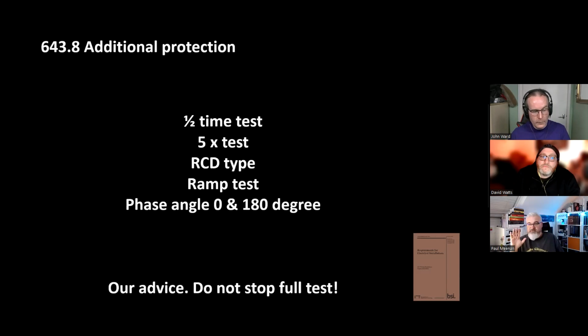The other thing I would really like to get on my soapbox about is, if we start cutting testing down to a minimum and we test at the terminals, then there is no point to it. I was taught that when I go out, I interrogate connection of the protective conductor at each point. Why? For safety of the fixed or portable equipment. I'm then also testing earth loop at each point. Why? To ensure the protective device will disconnect. I then test the RCD at the end of line or each point in the circuit. Why? To ensure the device works at every point in the circuit.